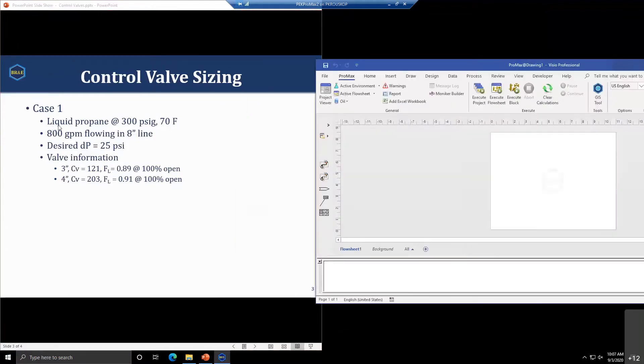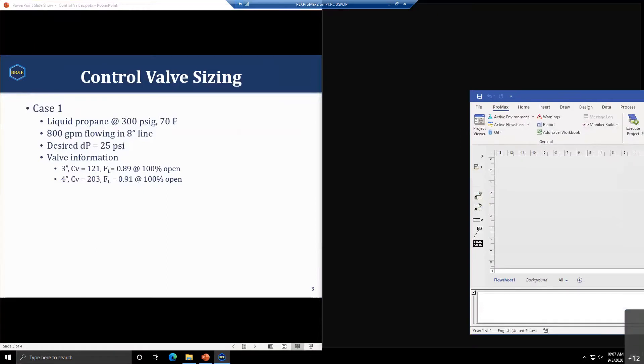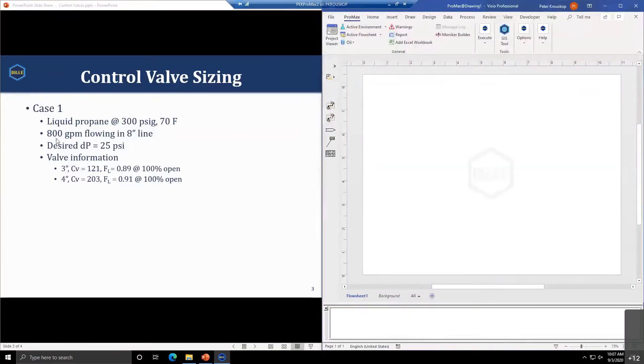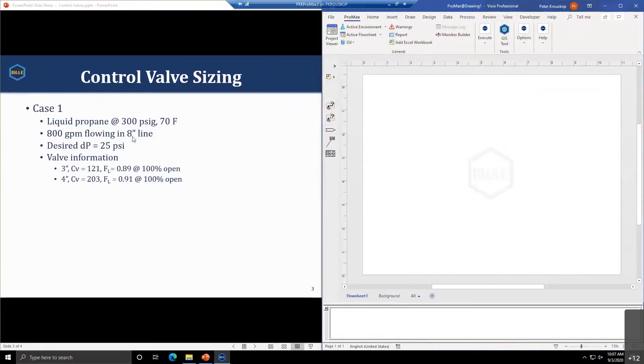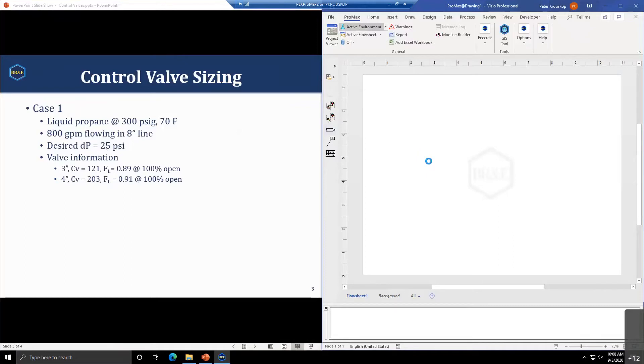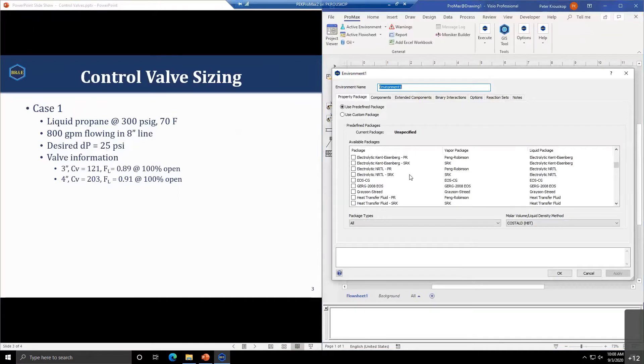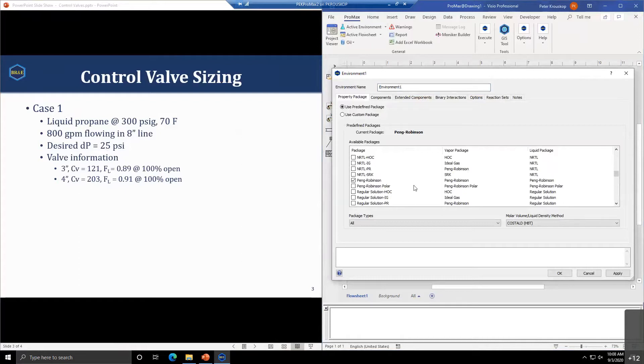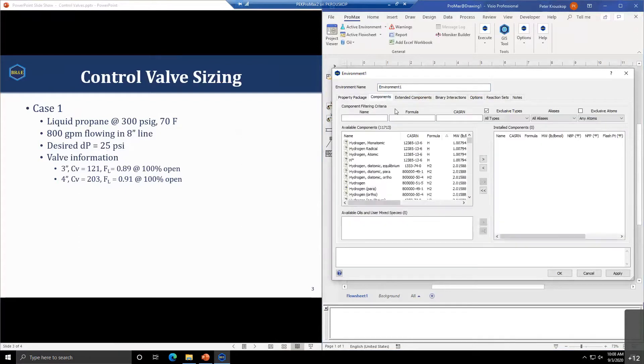Our first case is dealing with a liquid valve. We have liquid propane as our inlet with 800 gallons per minute flowing in an 8 inch line. It's a well oversized line, so they know they're probably not going to be operating with an 8 inch valve. They have a couple of valve options they'd like to figure out which one will work best.